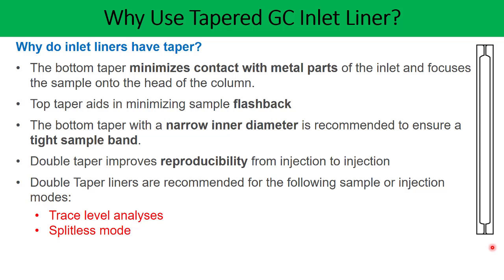In splitless mode there is not much carrier gas flow available inside the injector port, and hence the double taper can help you improve the vaporization and transfer of the vaporized sample onto the column. So it is always preferred to use the double taper liner in splitless mode. Third, for low boiling point compounds — compounds with a low boiling point get evaporated very easily and there may be non-homogeneous mixing of your diluent with these low boiling point compounds, especially if your diluent is a high boiling solvent. The double taper also helps in improving the homogeneity of this vapor, and hence it is preferred for low boiling point compounds.